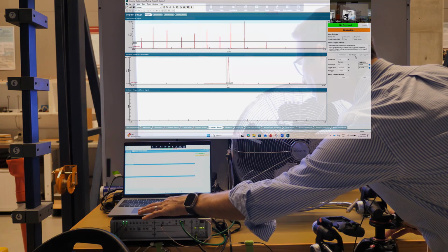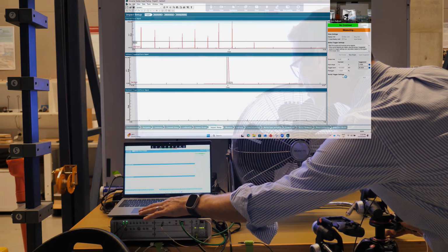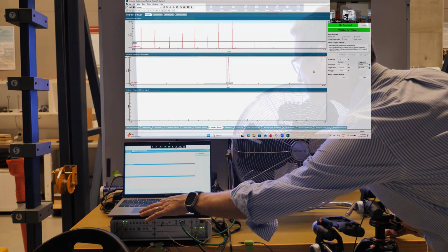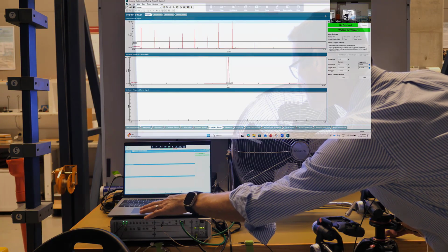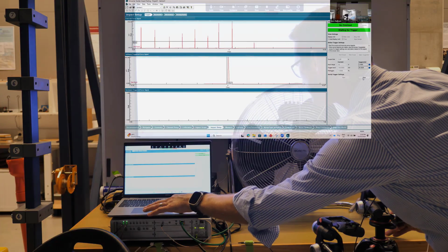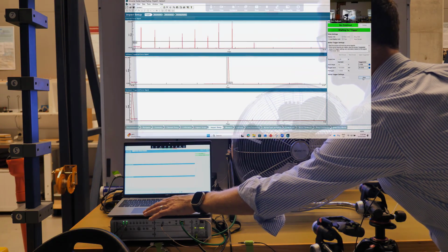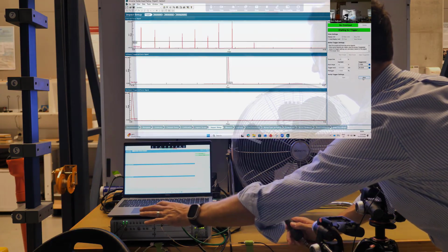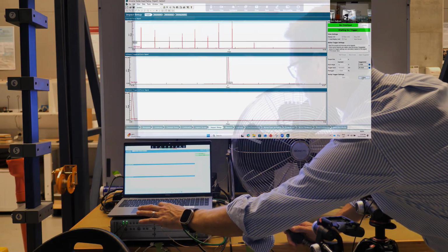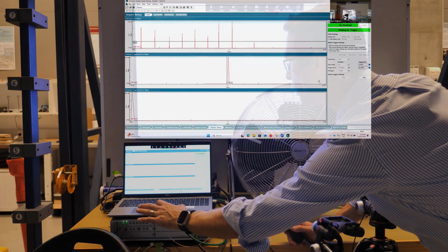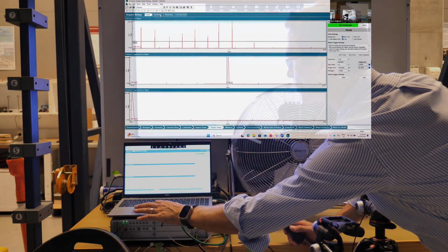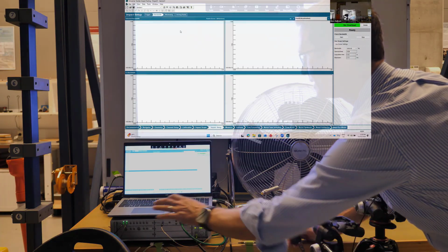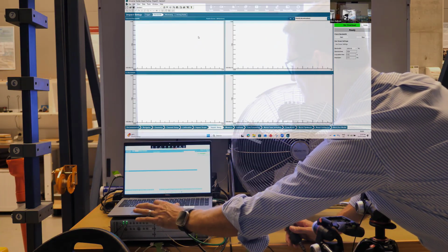So I'll stop the scope. The trigger settings have been suggested to be able to effectively capture these impacts. That's working quite nicely. You can see I've taken a soft tip because these resonant frequencies of interest are relatively low, I believe, so in the order of tens to hundreds of hertz. So I've chosen the silicone tip, and you can see the pulse width is quite wide.